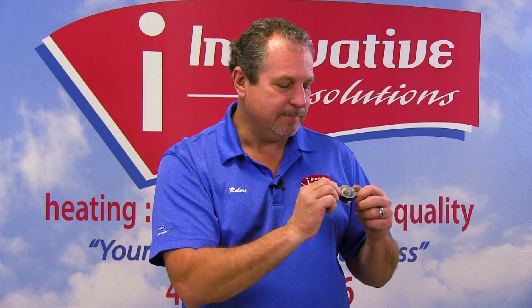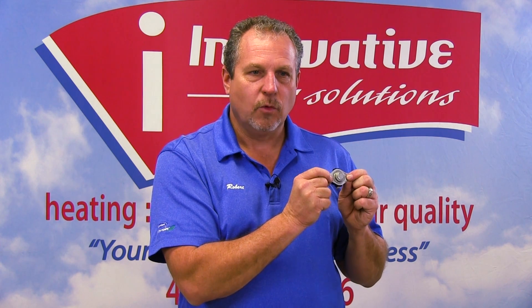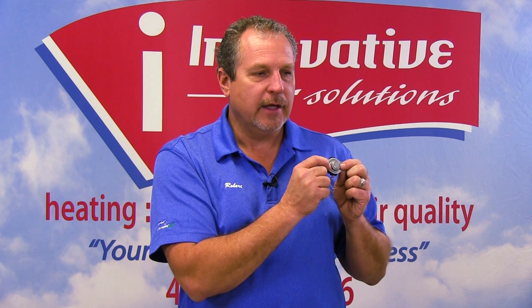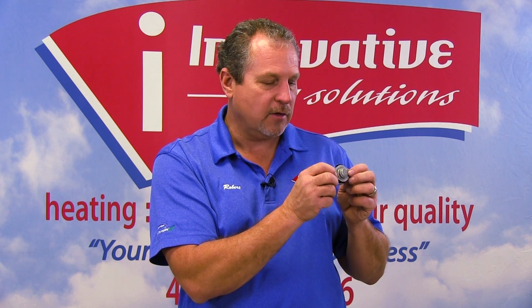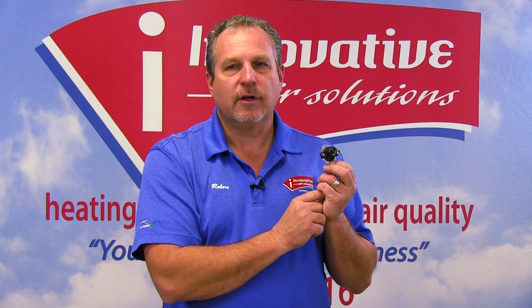On the back side we just simply have a little sensor. This is nothing more than a bimetallic sensor that will open or close based on temperature. It's two different metals put together that expand or contract at different rates, and that's how these work. So they're very mechanical — there's not a lot of high-tech operation to them, but they are very vital in protecting your customer's home.